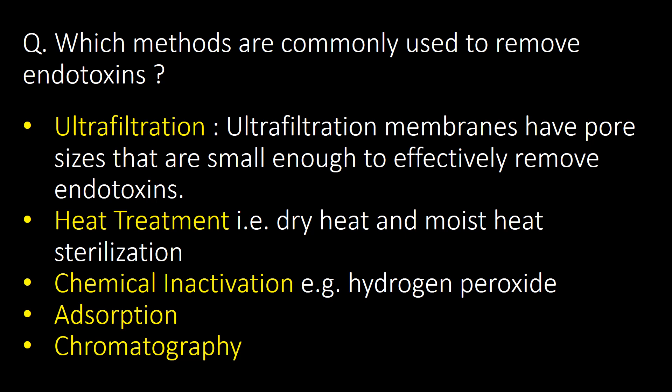Which methods are commonly used to remove endotoxins? First is ultrafiltration — this is a compulsory method for WFI treatment or WFI generation systems, as ultrafiltration membranes have pore sizes small enough to effectively remove endotoxins. Second is heat treatment — both dry heat and moist heat can effectively remove endotoxins. Dry heat sterilization is commonly used in depyrogenation tunnels and depyrogenation ovens. Third is chemical inactivation using hydrogen peroxide, and two additional methods are adsorption and chromatography.